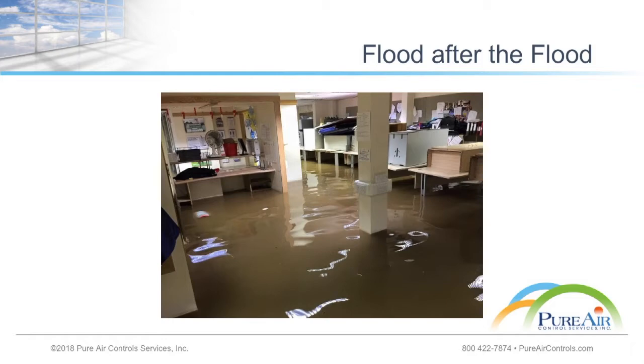One more thing I wanted to ask about, Dan - you mentioned buildings being under negative pressure in the context of water intrusion. Talk to us about that before you head out. Because of our air quality standards these days, we're infusing a lot of fresh air into the building, because we want to keep it either on a slight positive pressure or nearly neutral. If you're running on the negative side, cracks and crevices in the building will start pulling in water intrusion. So that's one aspect of your building envelope you should check regularly.